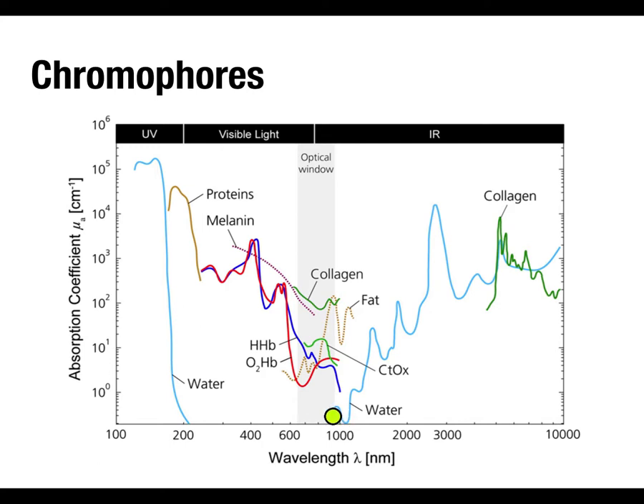The wavelengths used for near-infrared imaging are in the optical window, roughly the 700–900 nm range. An important reason to choose that range is that water doesn't absorb light there — it absorbs in the UV and higher IR ranges but not the near-infrared. Because our bodies have such high concentrations of water, that's critical — our signal isn't affected by water. Crucially, oxyhemoglobin and deoxyhemoglobin have different levels of absorption in this wavelength range, and they cross at a point called the isosbestic point.